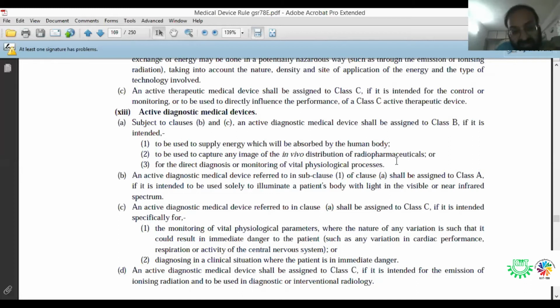And active diagnostic medical devices referred to in clause (a) shall be classified as class C if it is specifically for the monitoring of vital physiological parameters where the nature of any variation in such could result in immediate danger to the patient. So here we can say that if our head trauma screening device is used for the monitoring of very important physiological parameters, then our product is classified as a class C device because it helps in monitoring of vital physiological conditions. So from sub point 13 of the classification rule, active diagnostic medical devices, you can say that the head trauma screening device is a class C device.